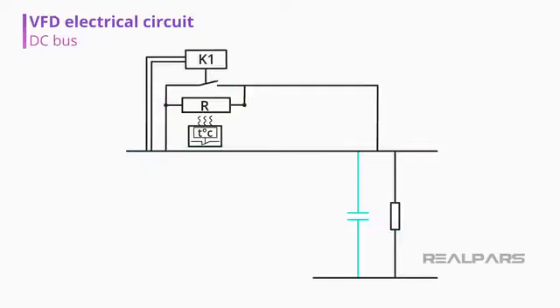In the scenario of the contactor not closing, and the VFD still starting the motor, the current flowing through the resistor will increase, which will overheat the pre-charging resistor. The thermostat will then act, and it will disarm the VFD due to overheating.